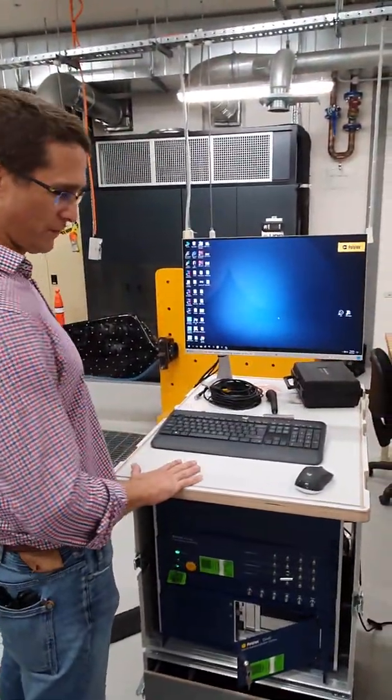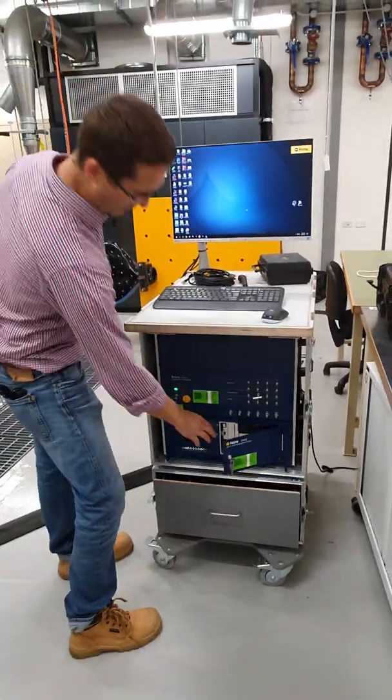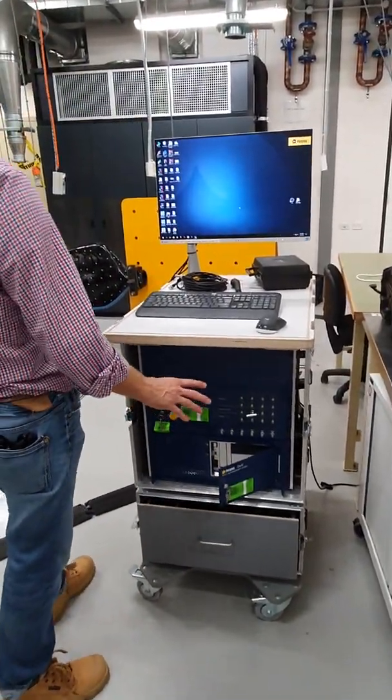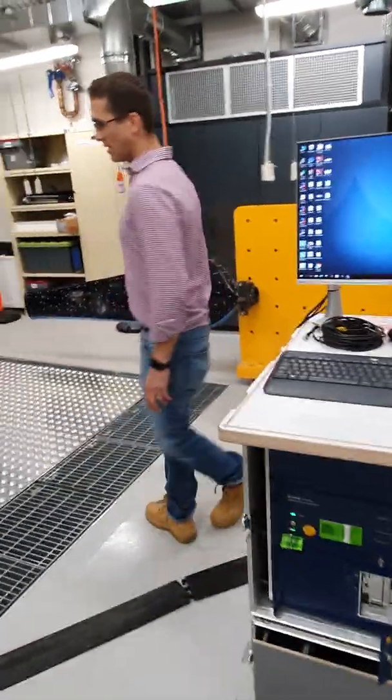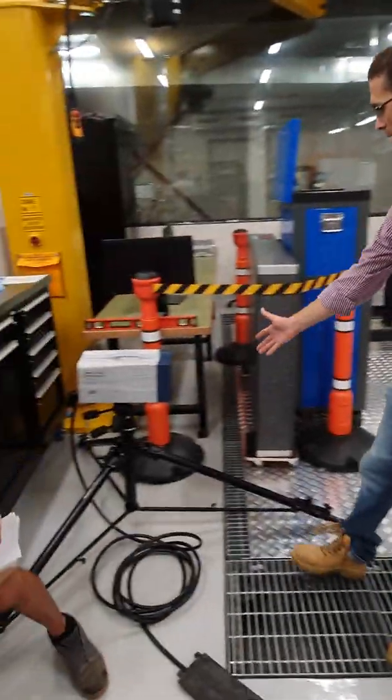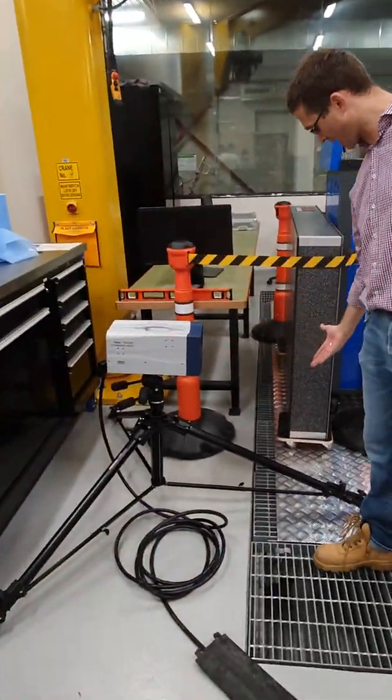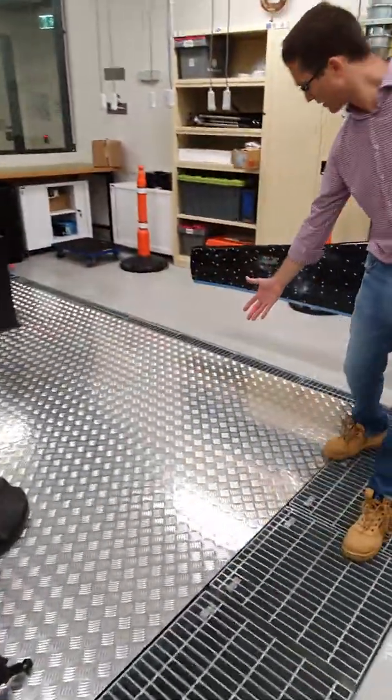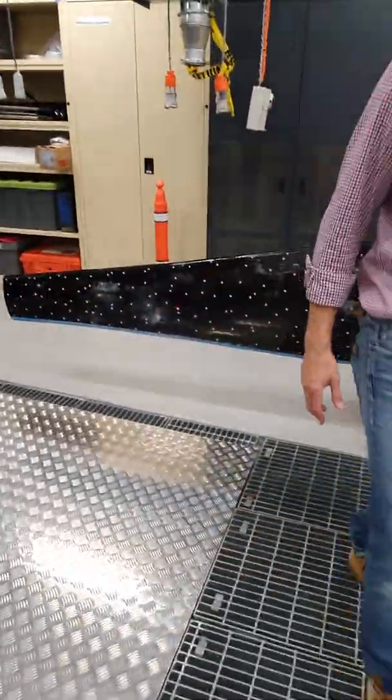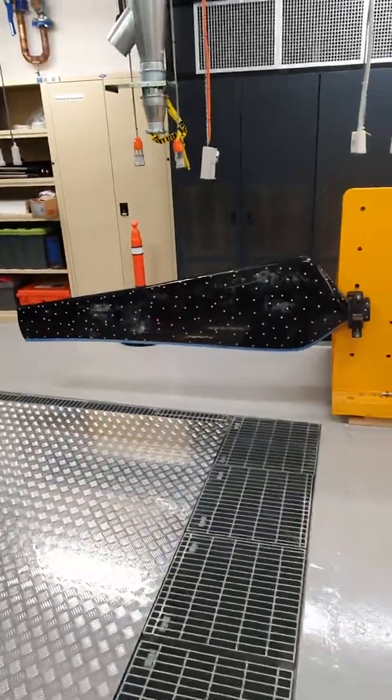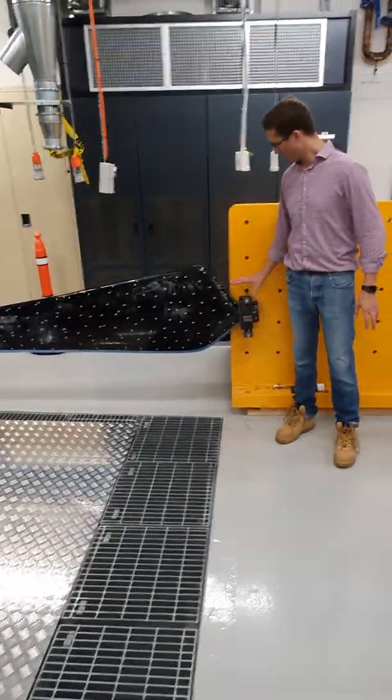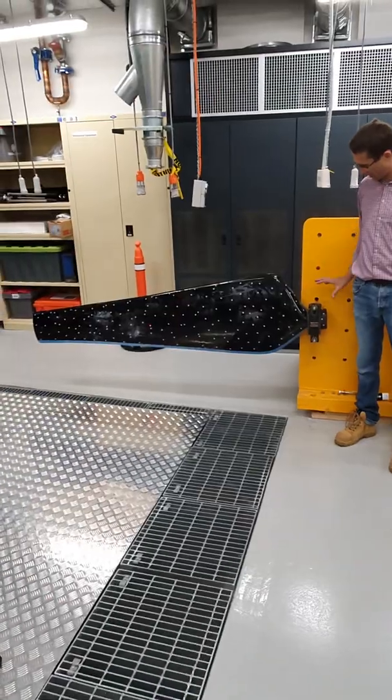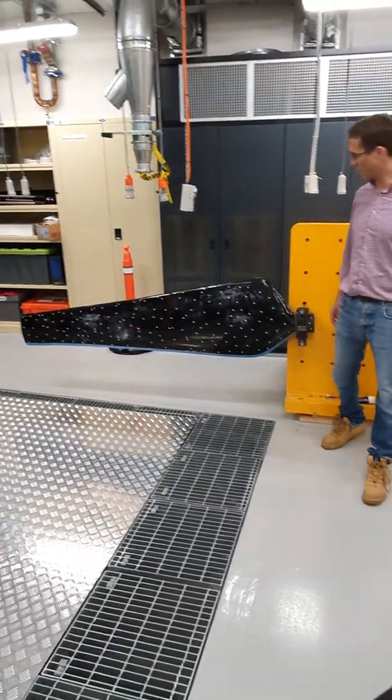We've powered up the PC first, I showed that in the last video, then we've powered up the vibrometer controller. The scanning head is sitting over here on a tripod and we've got geometry scanning laser, currently the red laser which is coming towards the test piece which is this blade, which is mounted over here on a rigid cantilever beam type fixed-free scenario.